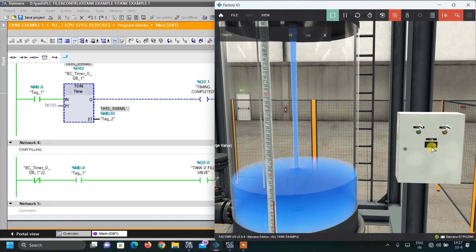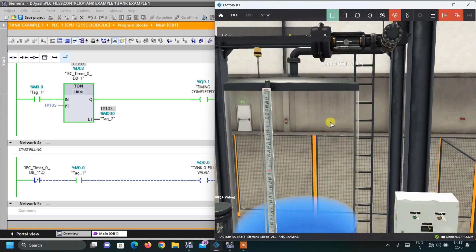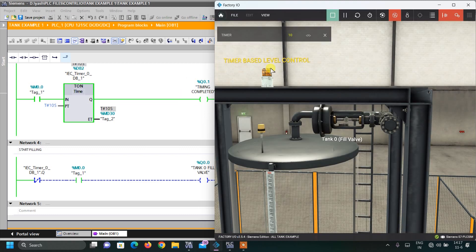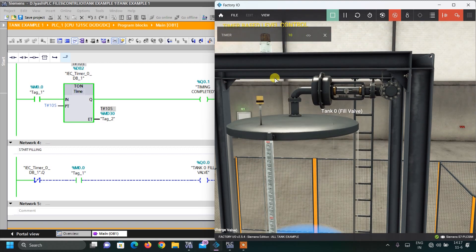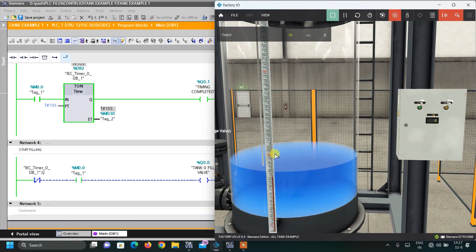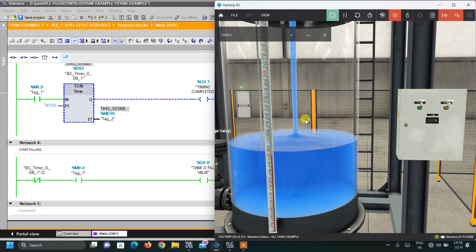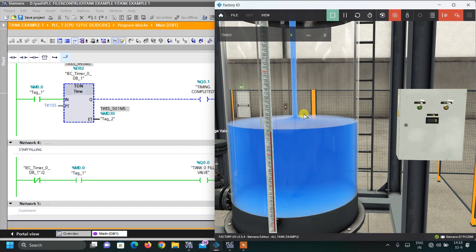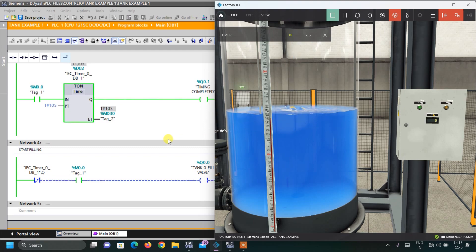You can see the timing value counting up. When timing is completed, the indicator at Q0.1 lights up, telling us the timing is done. If you want to fill for another 10 seconds, press the reset button — the timer resets and the valve turns off. Then press start again and it will fill for another 10 seconds. Each time you press reset and start, it fills for 10 seconds.